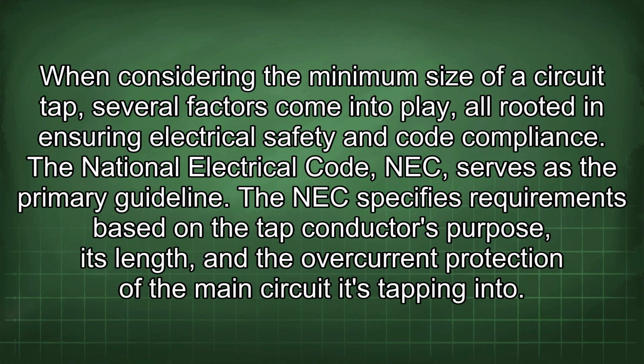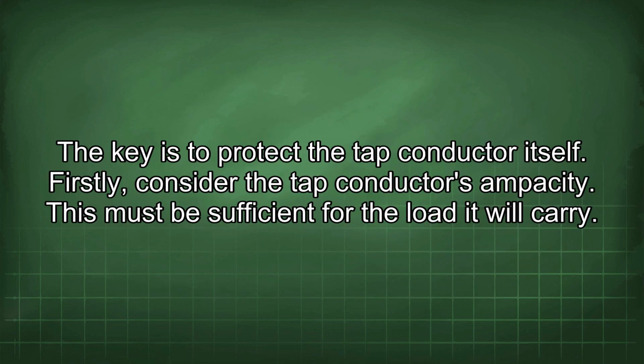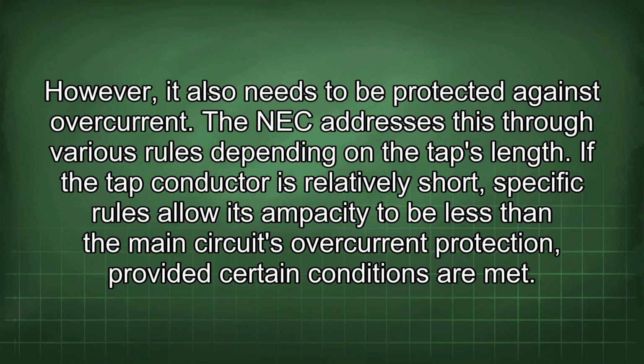When considering the minimum size of a circuit tap, several factors come into play, all rooted in ensuring electrical safety and code compliance. The National Electrical Code, NEC, serves as the primary guideline. The NEC specifies requirements based on the tap conductor's purpose, its length, and the overcurrent protection of the main circuit it's tapping into. The key is to protect the tap conductor itself. Firstly, consider the tap conductor's ampacity. This must be sufficient for the load it will carry. However, it also needs to be protected against overcurrent.